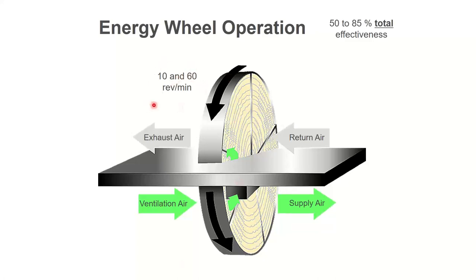This is basically like a record player. If you had an old 45 record, well, nobody knows what I'm even talking about. If you're old enough to know what a 45 record is, thank you. It's rotating at that type of speed, 30, 40, 50 revolutions per minute. It can't go too fast because then it won't be able to transfer the BTUs quick enough. And it can't go too slow because then it's not going to do it either. It's got to be just enough time for the BTUs to get inside this heat exchanger and then move to the other airstream.